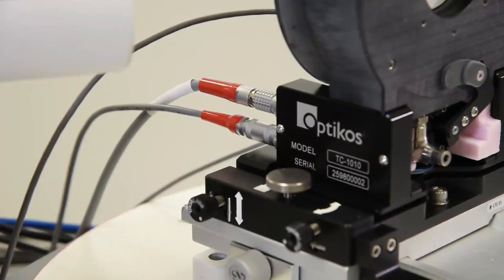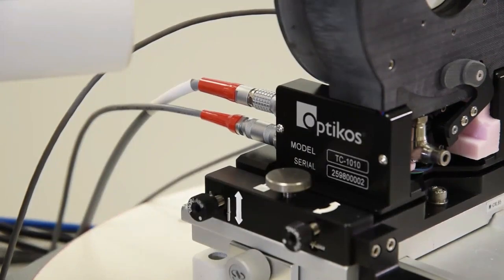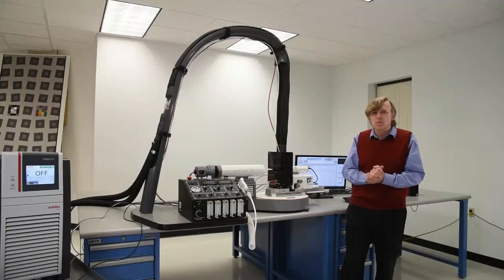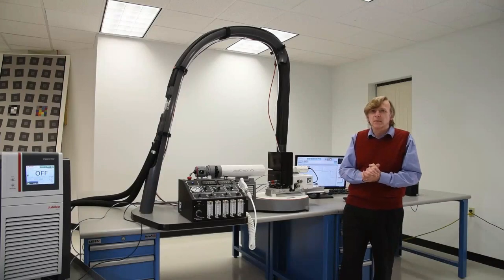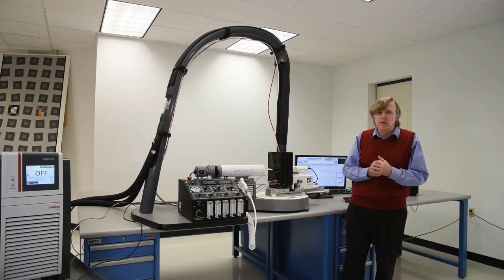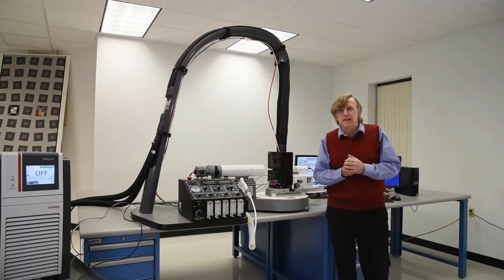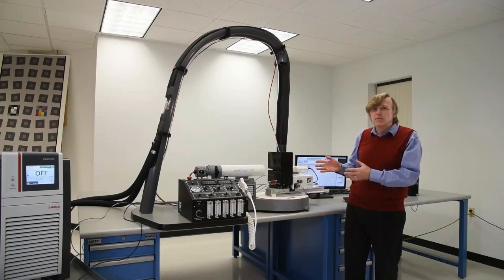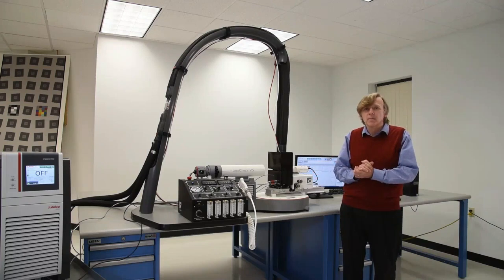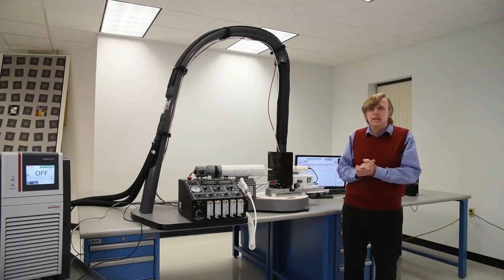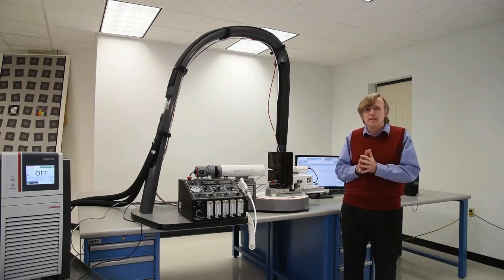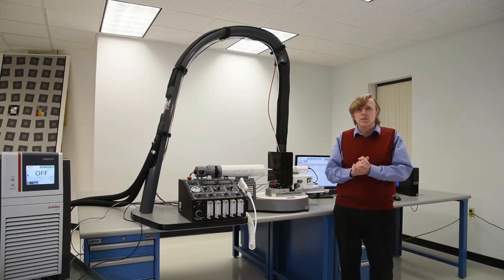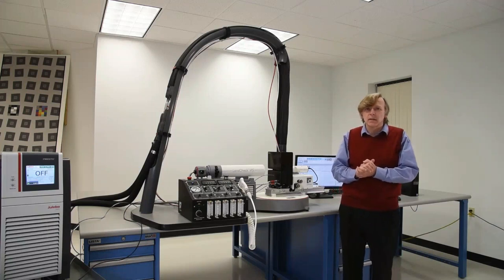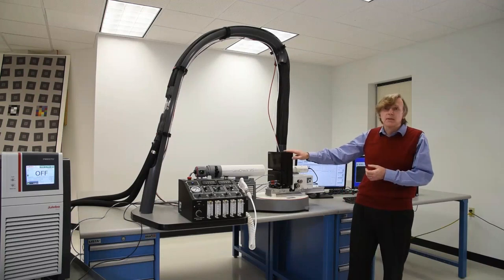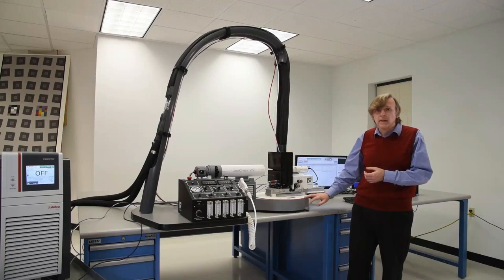The TC1010 is a thermal chamber that is intended for use with small form factor, wide field of view lenses. Larger lenses may be accommodated by the TC1050. Both are adaptable for use on the LensCheck or an OpTest system. Very large lenses must be accommodated by the TC1150, a thermal chamber that must be mounted on a full-size OpTest bench. The setup we have here shows a TC1010 on the LensCheck.